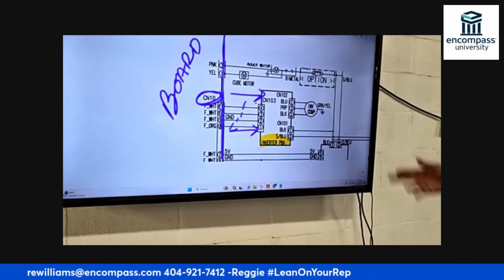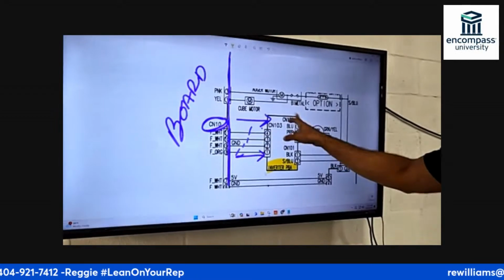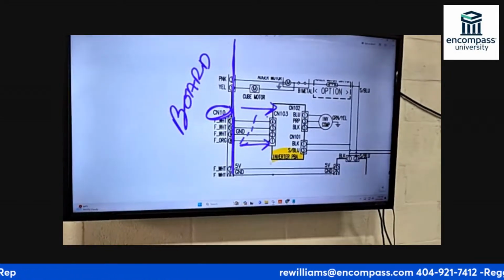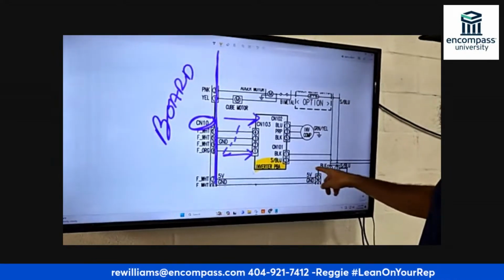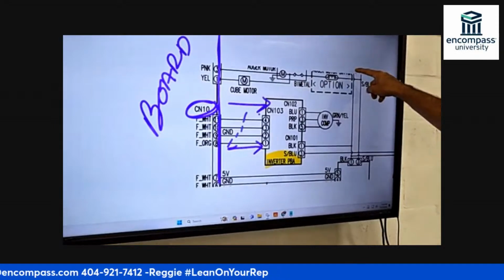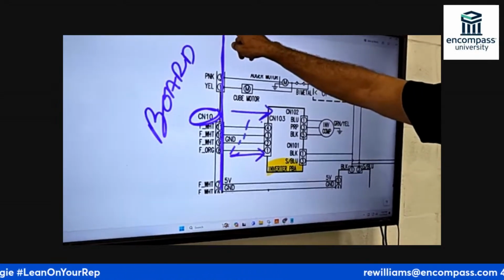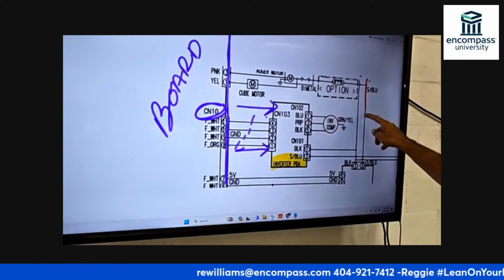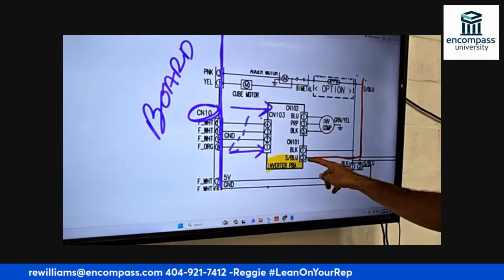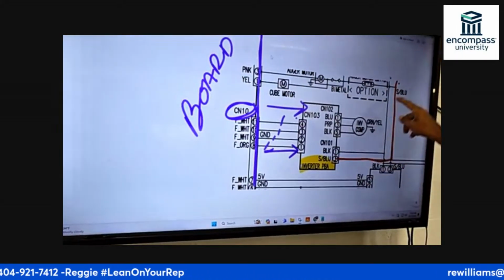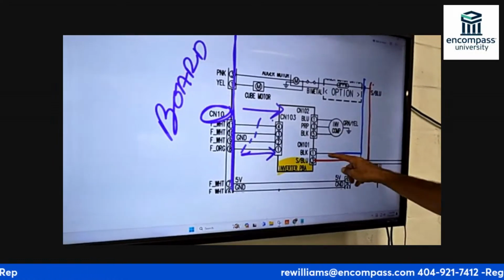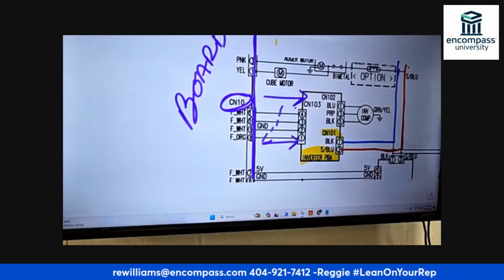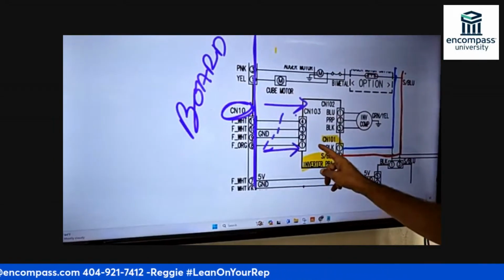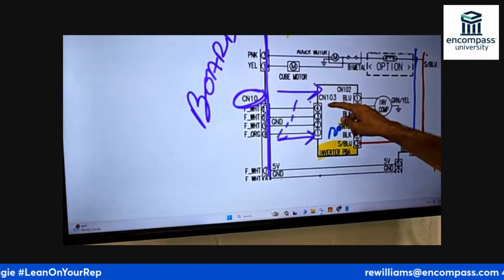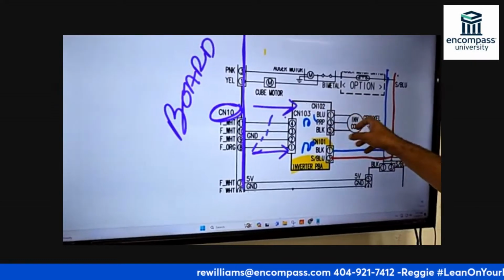This inverter also is communicating with this board. There's communication going on. There's all types of stuff happening in here. But right here, it's getting L1 and neutral. It's getting L1, and it's getting neutral. And that's taking place at CN101. So an important characteristic of this inverter is that it's getting 120 and it's getting DC too. So now it's sending my voltage to the compressor through these wires here.